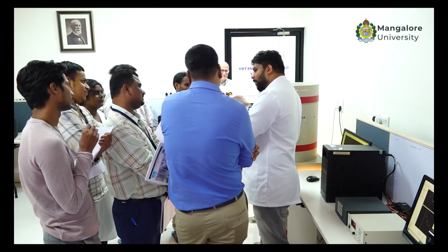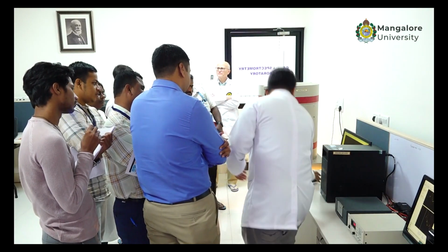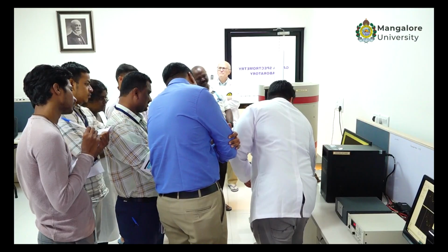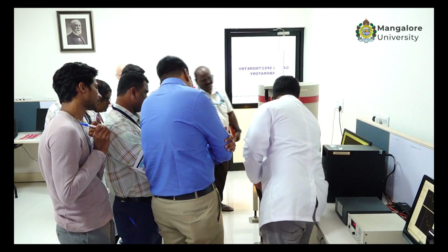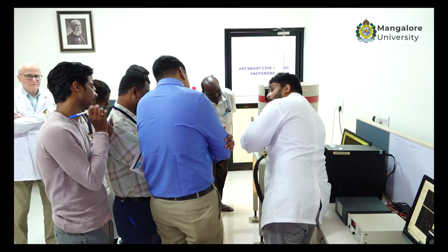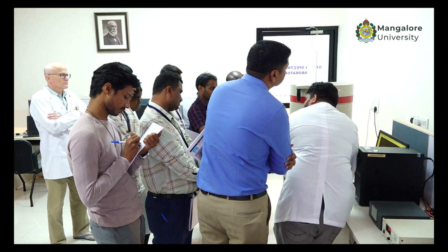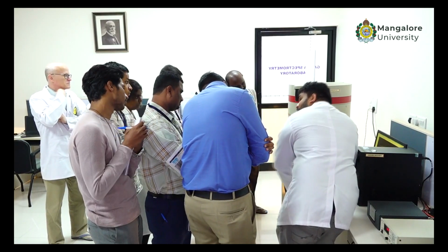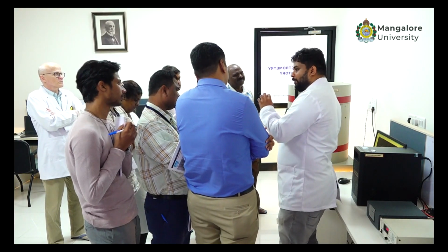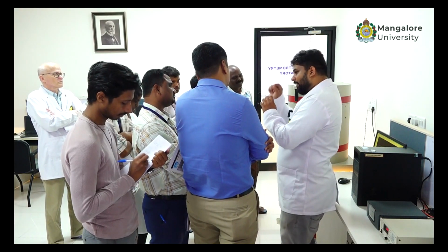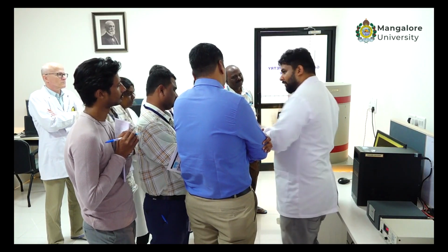Now those boxes, or that spectrum, is viewed over here. For example, I'll show you from the beginning. This is our starting peak. This is channel 326, which corresponds to 32.6 kilo electron volt. The next channel is 327, which corresponds to 32.7 kilo electron volt. So one channel is 0.1 kilo electron volt. Even if there is an energy difference of 0.1, it can still resolve it and put it into different channels.